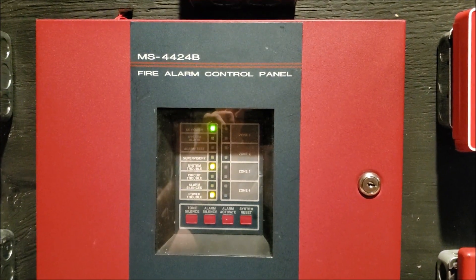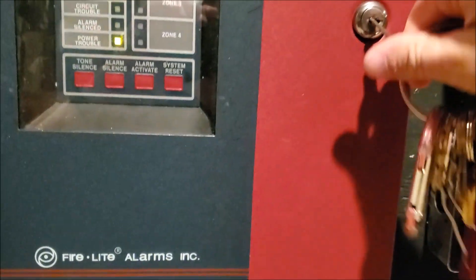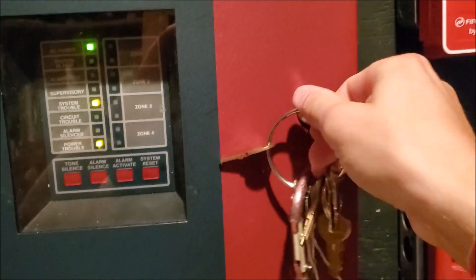The control unit itself is a Fire-Lite MS-4424B. I have all the keys to the unit right here. The great thing about these Fire-Lite panels is that the door can actually just come off for easy maintenance. So usually when I open up the door, I like to take it off. As you can see, there are two NAC circuits and then there are four zone circuits. You can see I have resistors over the last two zones so it's not in trouble for the circuit. And you can see the wiring coming out of here — it goes into that hole behind the board, and then it goes to the devices.